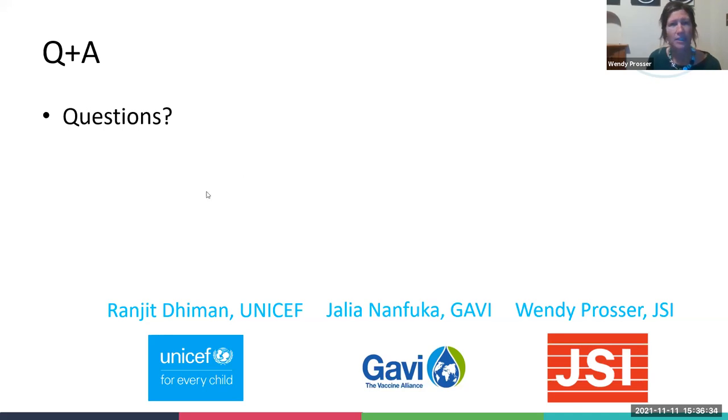Let's move on. There were a couple of questions on 30 DTRs. Ranjit, I'm going to put you on the hot spot. A couple related to the shelf life and the potential of changing out batteries or having a different technology with that. Yeah, so this also brings one piece of news for everyone: there's a new model of 30 DTR from Berlinger. It's the FT2E, which has a 5-year life. In fact, the old model, the FT2, is no longer intended to be produced from next year onwards. So it's going to be a 5-year battery from now on.